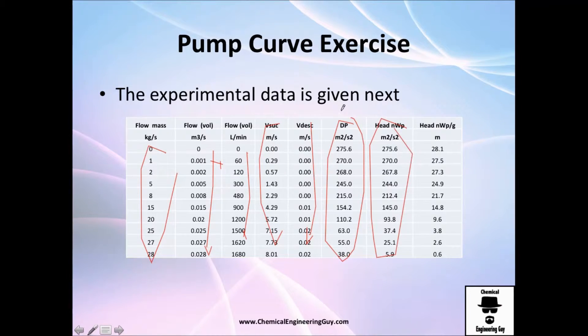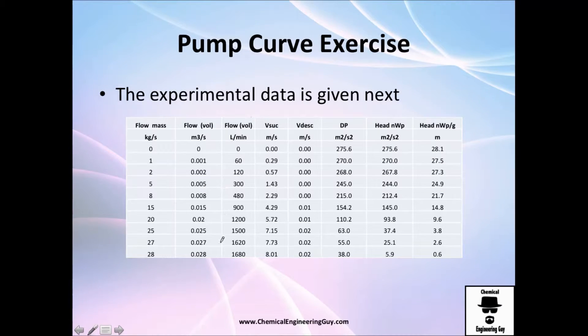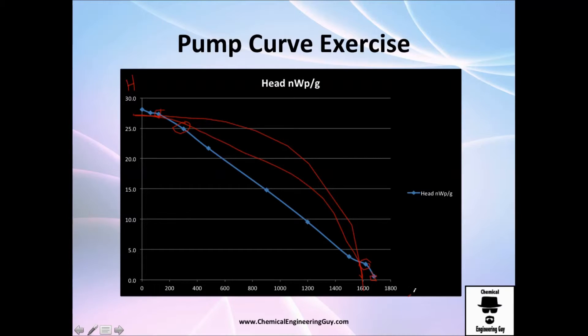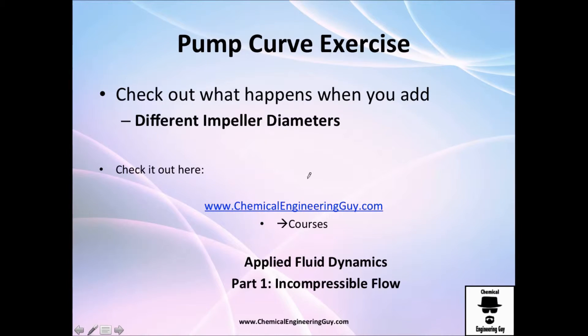The head developed is essentially the change in pressure plus the velocity head. I want you to graph these values — the flow rate on the x-axis and the head on the y-axis. Normally a pump curve looks something like this, or even concave like this. This is a little bit concave; you can see different values because it's real data. This is our head in meters, and this is our flow rate in liters per minute — and that's what I wanted to show you in this video.